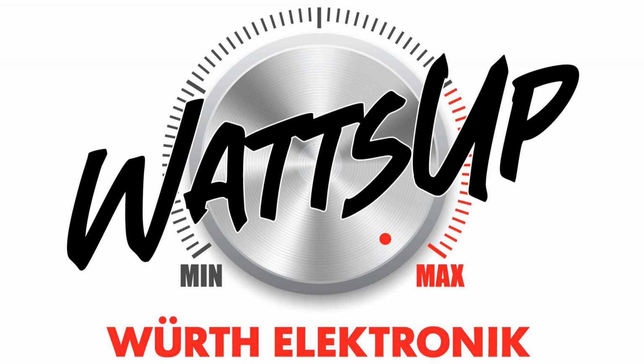So for perfect coupling, the coupling factor would be near 1. Of course, perfect coupling would be 100%, and the K factor would be 1. But in reality, we find values from 95% up to 99% or 99.5%. But 100% is not possible to reach. So the higher the coupling factor, the lower the stray inductance. Also shown here is how it's measured.